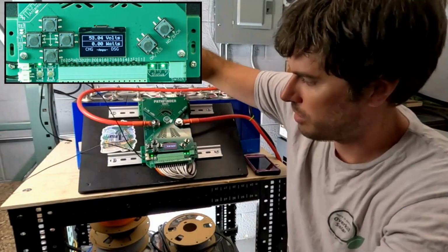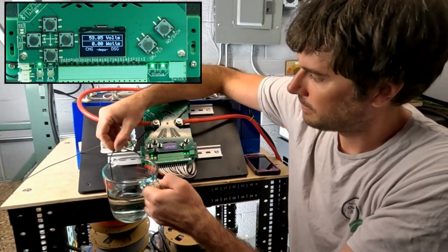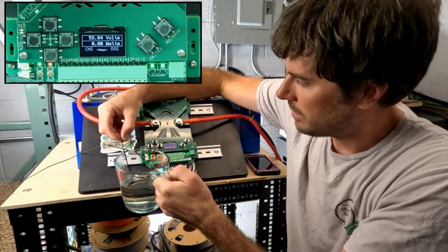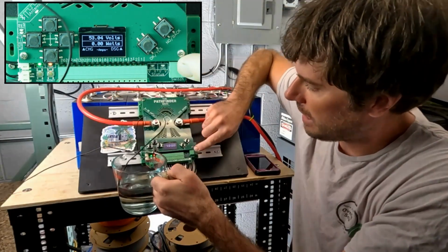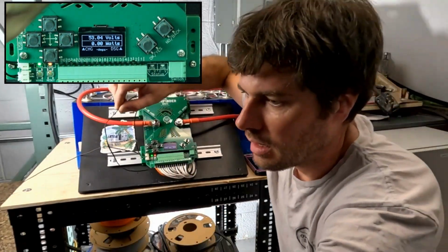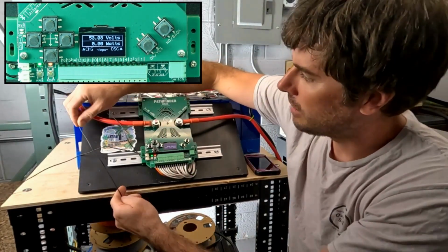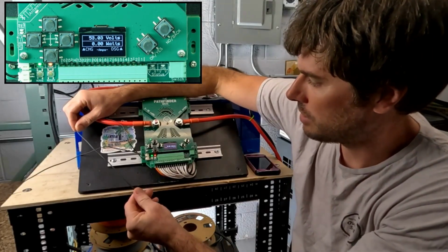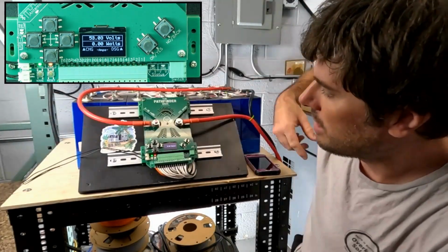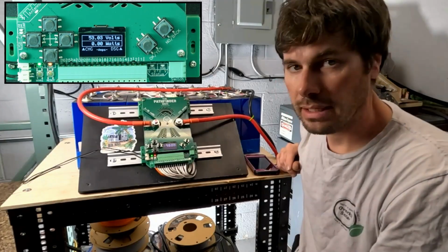Let's test that one more time with probe number 2. There's our fault light, and there is our outputs shutting off. So now we have both probes correctly reading the high and low temperature cutoffs. I'll just cool that off again, and we should see the outputs re-enabled. The delay is 15 seconds.